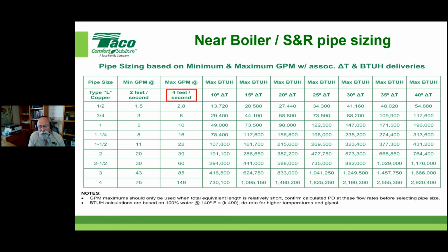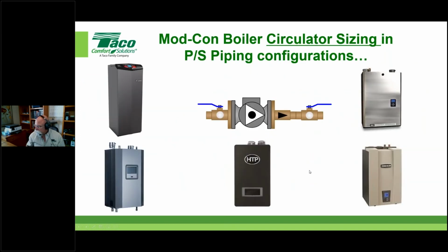Now you might not want to do that, or you might, depending on how good you feel about what's written in the boiler's manual, etc. I'll refer you back to that every time. So in reality, it's impossible to oversize a header within reason. If the flow rate says 1 inch and you want to put 1.5 inches, it's only going to be of benefit to you. It won't hurt you much.